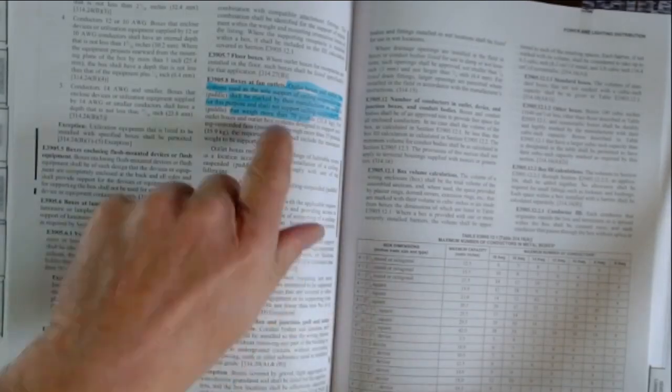Yeah, I had the question, how many of these THHNs, 12 gauge, could I fit in half-inch conduit? The number's 8. That's where that popped up. Outlet boxes designated for ceiling fans: 70 pounds is a ceiling fan. 70 pounds is the limit. Damp and wet locations: offset your panel by 1/4 inch from the wall.